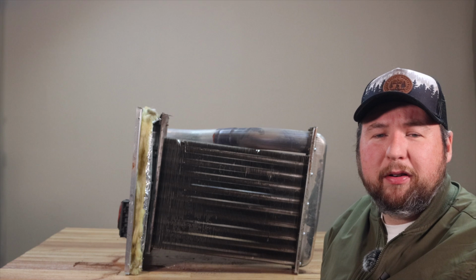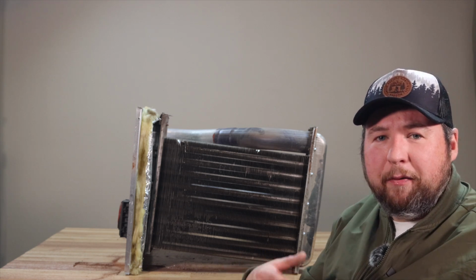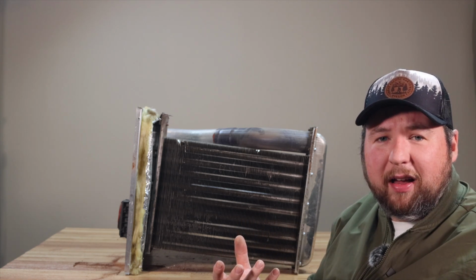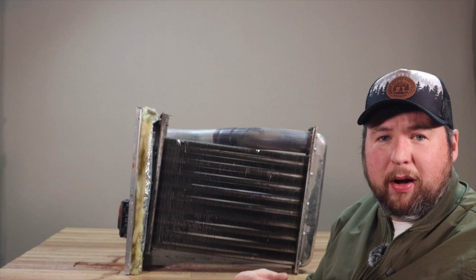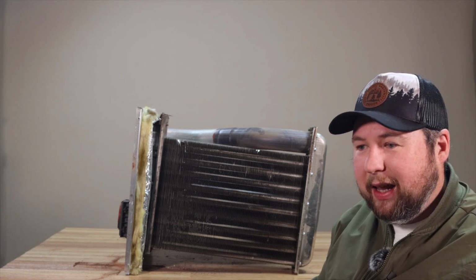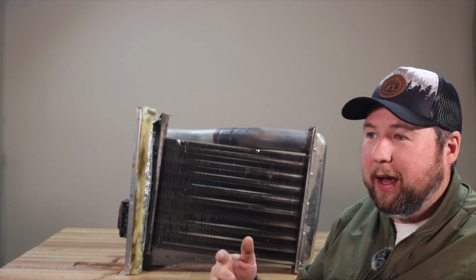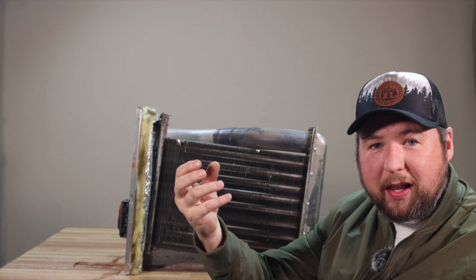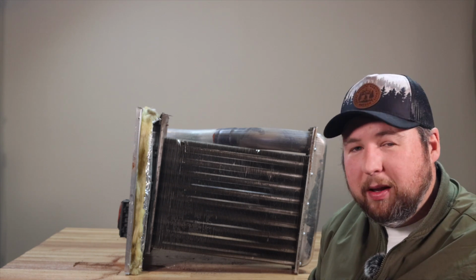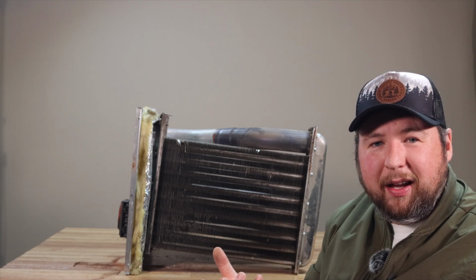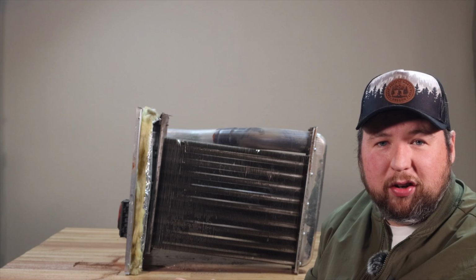But because of that lower temperature, any moisture that's vaporized in that exhaust stream is going to go ahead and condensate back into a liquid. And that's why it's very important that your exhaust pipes are pitched downward. That way, if any condensation happens within the exhaust pipe, it can just run back into the drainage system. Otherwise, it gets trapped, and then it can cause a restriction in the exhaust.